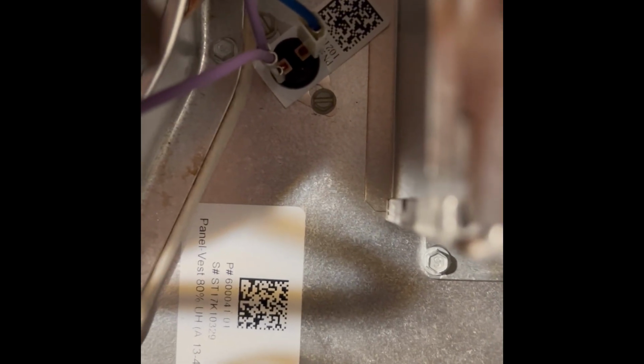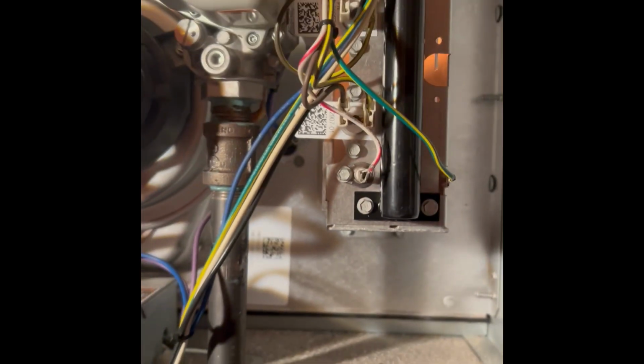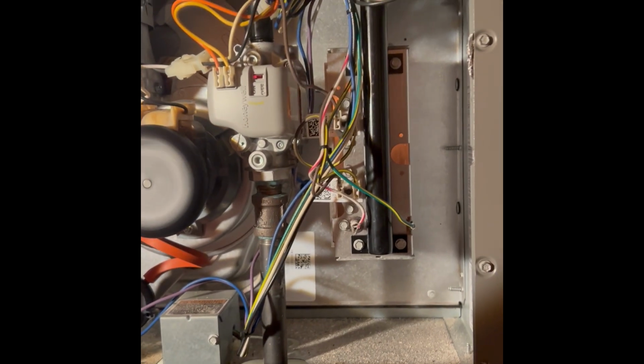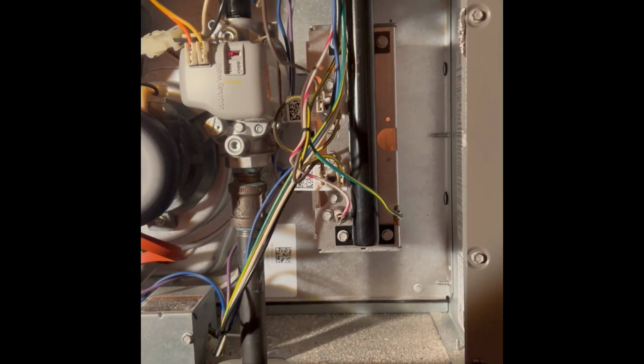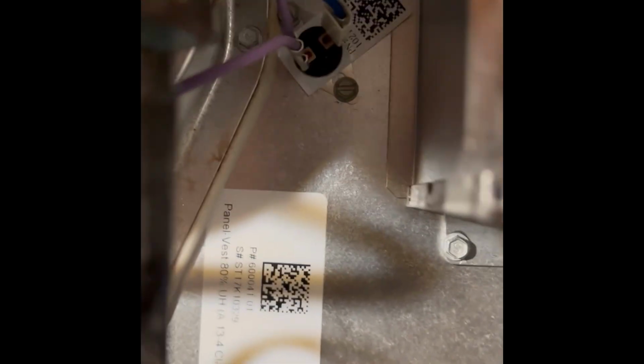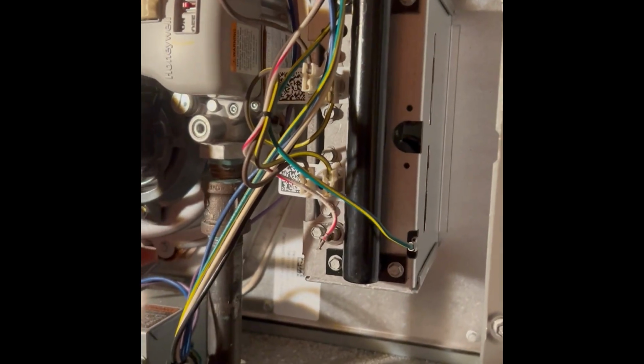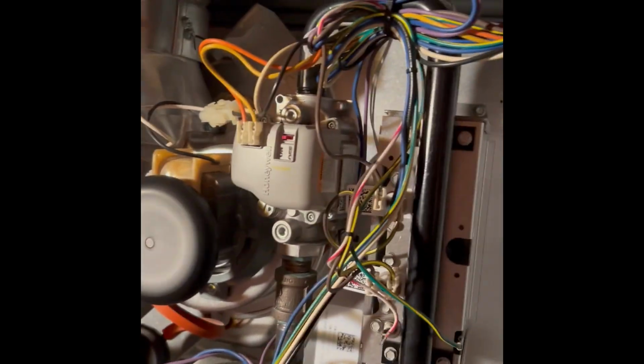What's happening here is this is a gas furnace. And this switch right here is a limit switch. It's the main limit, and it stops the furnace from overheating. We don't want the furnace to get too hot and cause a fire or something. That's the switch that opens and turns off the gas. As I'm filming this, the gas is turning on and off, and that switch is opening. The fan is running, so it cools it back down, and then it closes again. And that is caused by not enough airflow.